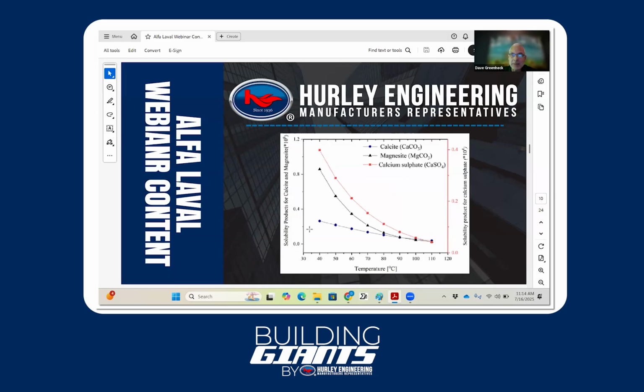In comfort cooling for HVAC, cool temperatures of 40 to 60 degrees won't show as much scaling as fast, but heat that water up and you'll get significant scaling, even if the water's pretty clean and not very hard. Think about boilers, humidifiers, even cooling towers—you'll get scale because the temperatures are warmer. In any system, this is a problem that needs to be considered.